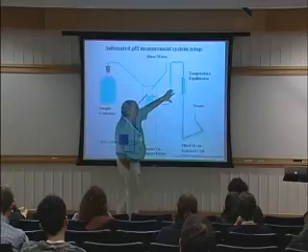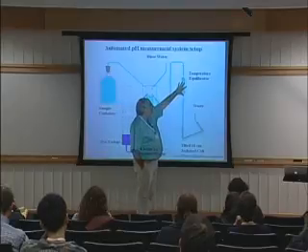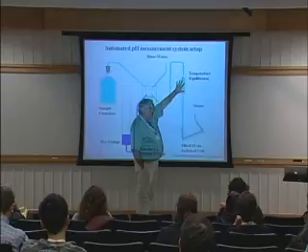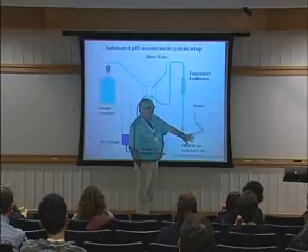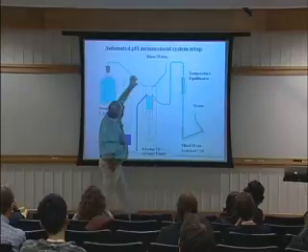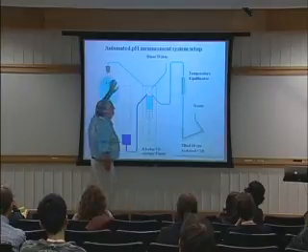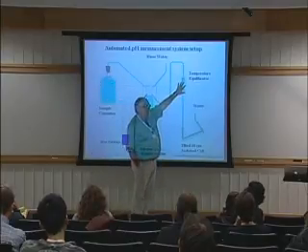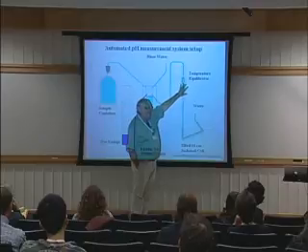About every 3 minutes, this can run a sample. Partly because this gadget brings the temperature to within 1/10 of a degree, or 1 or 2/10 of a degree, before it ever goes into the cell. So it doesn't have to sit in the cell long to be at stable temperature. But then you need this bottle to be within about 5 degrees or 4 degrees of where you want to be. Otherwise it doesn't work.